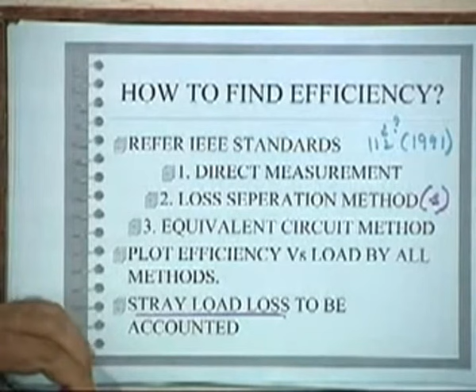And the third method is called the equivalent circuit method. If you know the equivalent circuit parameters, then also you can calculate the efficiency at different loads. That is a theoretical way. So these three methods, you can plot efficiency versus load by all the methods and see what the difference is. Okay. Now one more thing in actual practice, especially if you are talking about megawatts of motors, the critical issue is stray load loss, which is not accounted for. So you will often find that the output power that you get is less than what you would expect, right. For a given input you expect a certain output by loss separation, but you are not getting it. So this has to be accounted for.